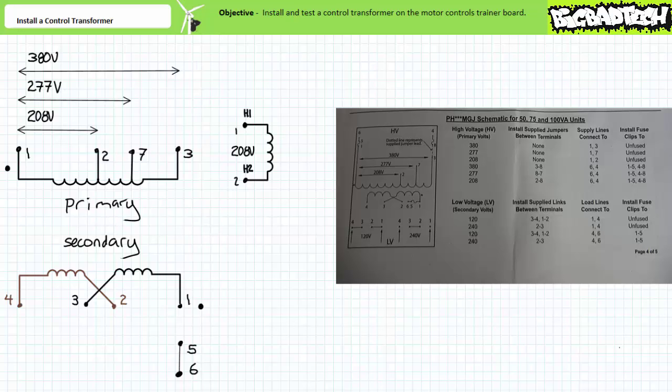Note this particular control transformer can also be utilized for 277 and 380 volt systems if a technician were to make use of the other primary terminals. This versatility allows a manufacturer to distribute this particular control transformer to different customers making use of different voltage schemes or located in different countries.